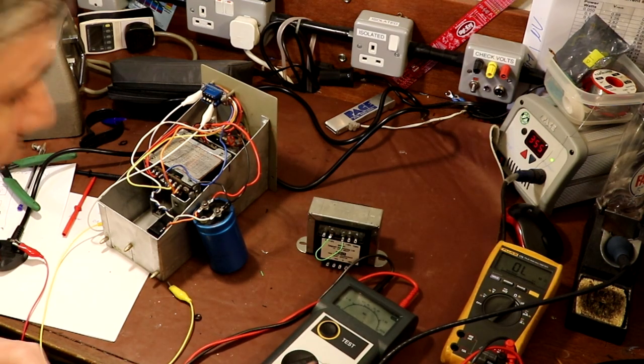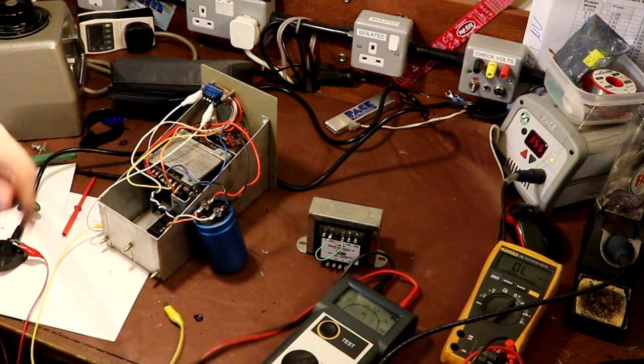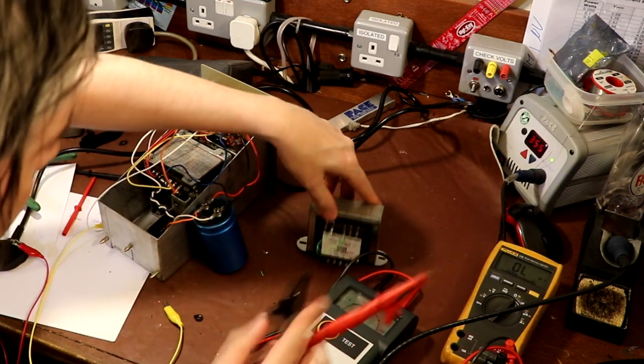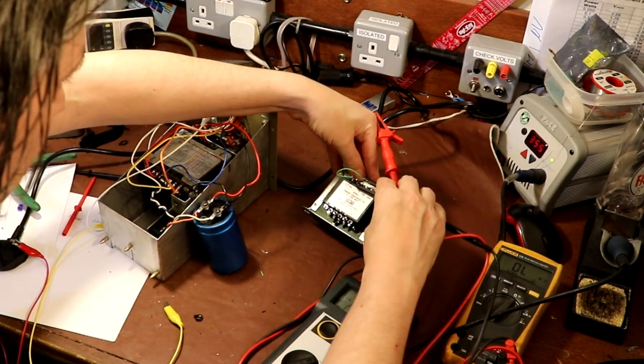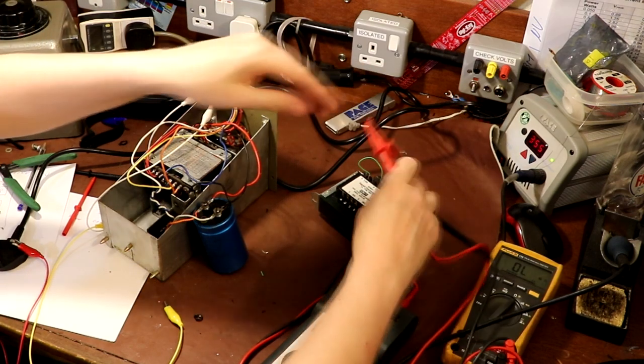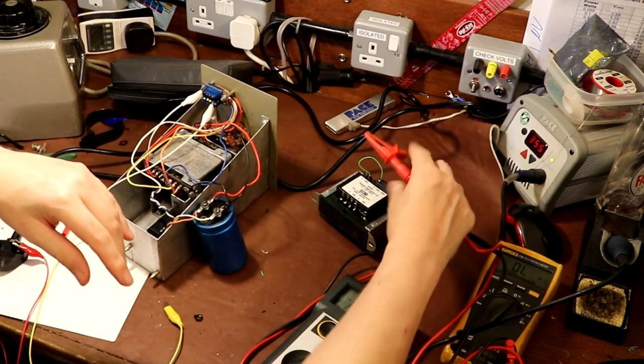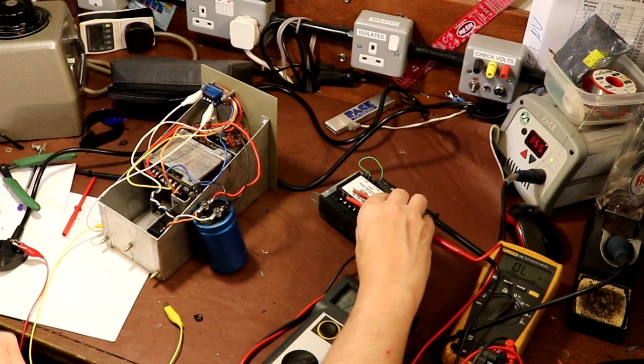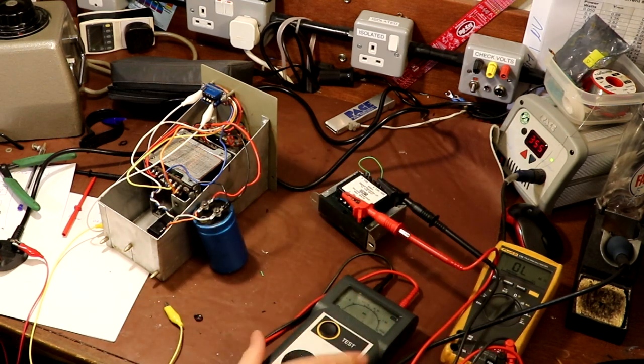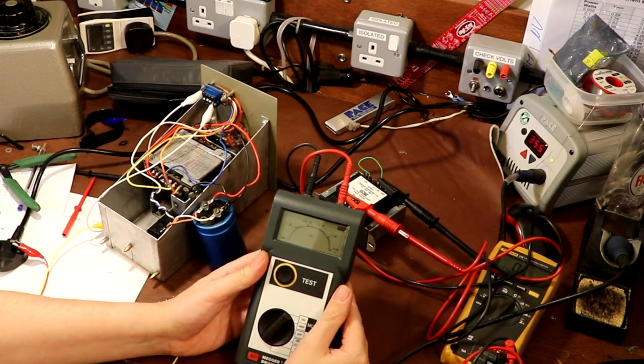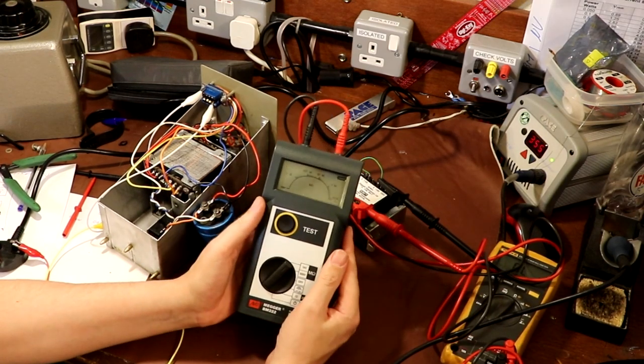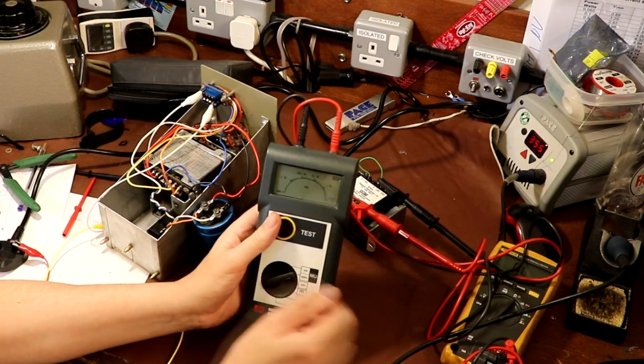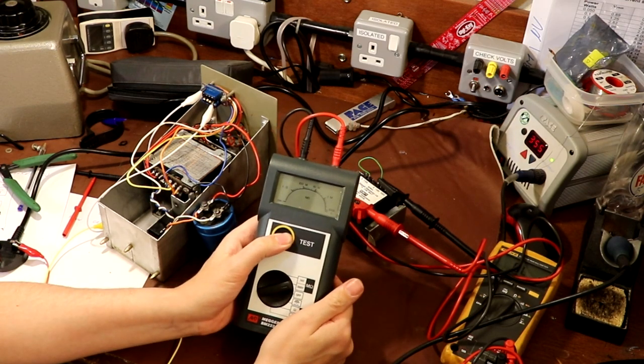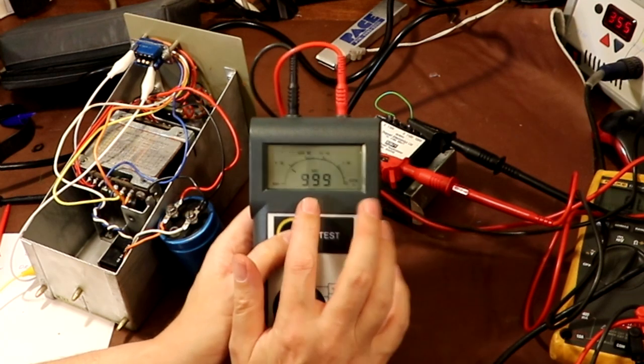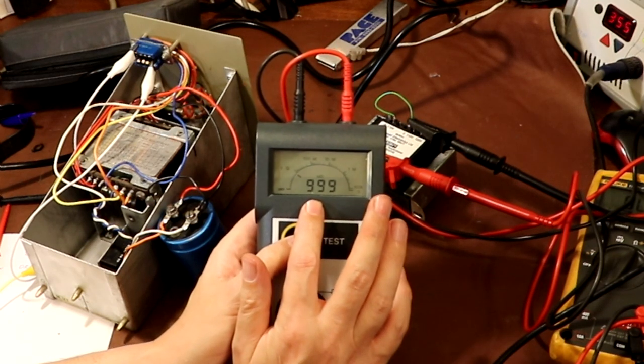So I'm going to use my megger here to do an insulation resistance test. All you need to do is put one connector on the primary windings and the other connector on the secondary. What you should be looking for is, the higher the reading the better. So let's set that off. In fact, I'll put it on 500 volts.